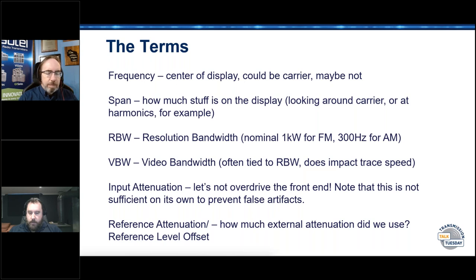RBW, that's one where we'll see a lot of people run into trouble. Generally speaking, to oversimplify it a bunch, the lower that value, the more accurate the measurement's going to be, because you're looking at a lot more points along the span than if you have a big one.